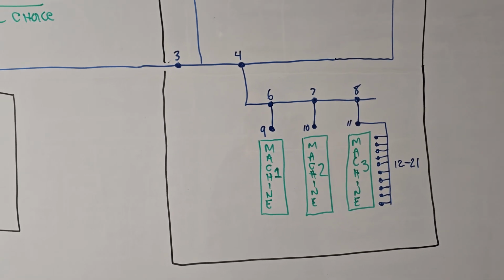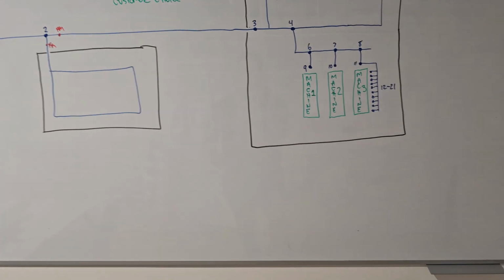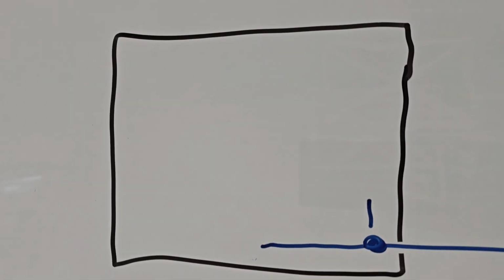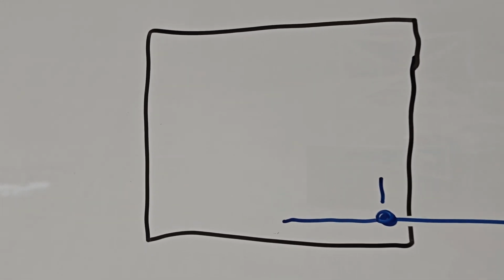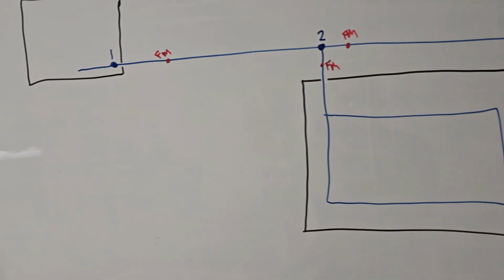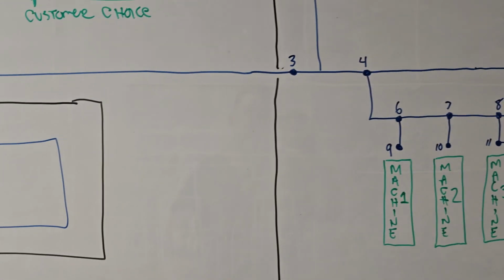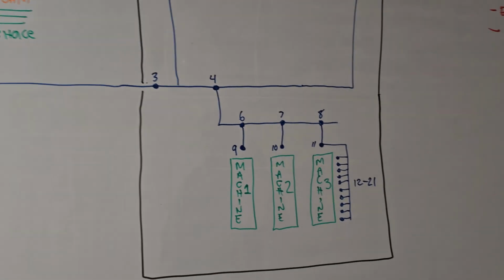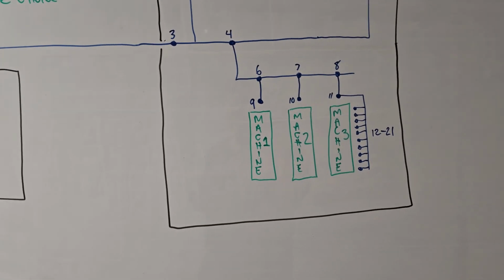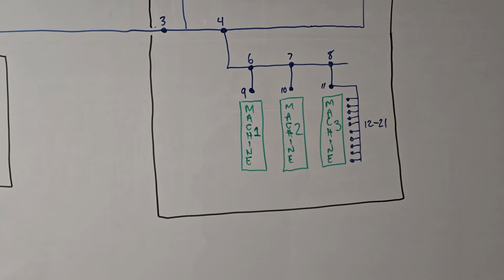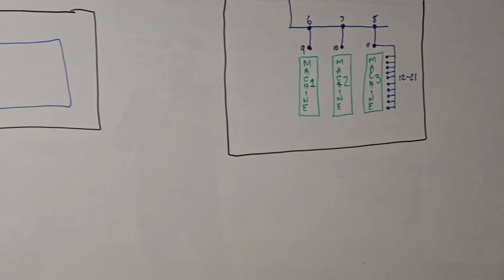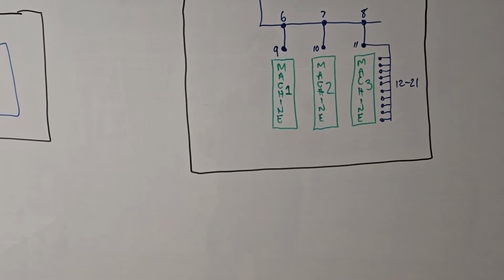So after we learned what the customer's problem is, we did a walkthrough assessment. We collected all the data on the equipment: the compressors, dryers, filters, receiver tanks, pipe sizes, layouts. We walked through and looked for instrumentation. We interviewed stakeholders, and we tried to gain as much information as we could through what we call the observation method. After this, we have pictures, videos, interviews, and machinery data.